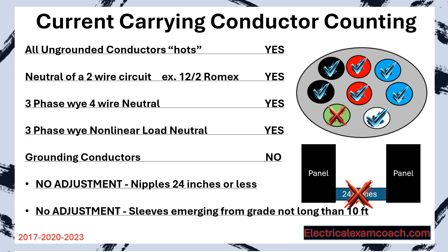Just a quick recap: we're going to count all ungrounded hots, we're going to count most neutrals, we're not going to count grounding conductors. There are no adjustments for nipples 24 inches or less, and there are no adjustments for sleeves emerging from grade not longer than 10 feet.